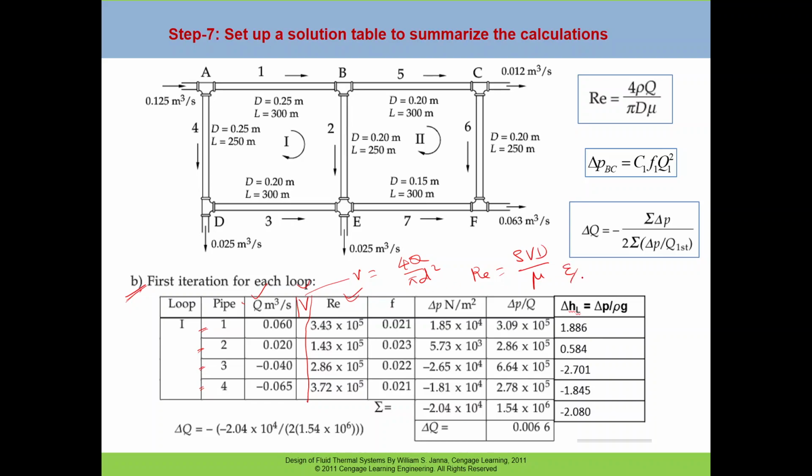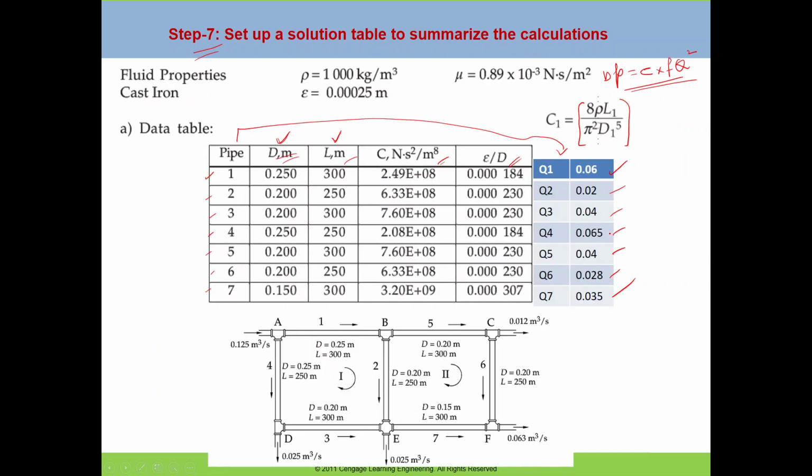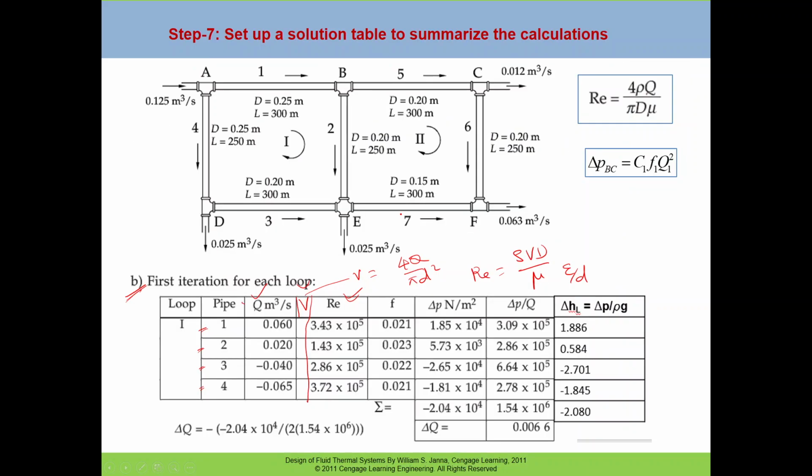And we know the epsilon over d for each element, because we prepared this table showing the epsilon over d and the c for each element. So we already prepared elements 1, 2, 3, 4, and we can use them directly. So we know the Reynolds number. The Reynolds number can be calculated as rho v d over mu, and then epsilon over d shall be checked: what was the value for line number 1, and what is the value for numbers 2, 3, and 4.